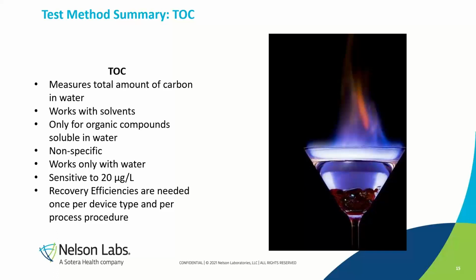TOC, again, we'll just kind of re-summarize some things already talked about, but it measures the total amount of carbon extractable with water. So if there's that IPA, it'll go into that water extraction. Again, it's a 30-minute sonication, and then instead of evaporating, we pull off an aliquot and put it right on a TOC analyzer that produces that carbon microgram per device. Well, it'll be a microgram per mil, and then the lab will calculate it into micrograms per device, or per surface area, if that's preferred. Like gravimetric, it's non-specific. It's a water-only extraction. It has very nice sensitivity, and a recovery efficiency is also required here. Just once per device type and per method, and then it can kind of be held on file if more testing is needed at a later point.